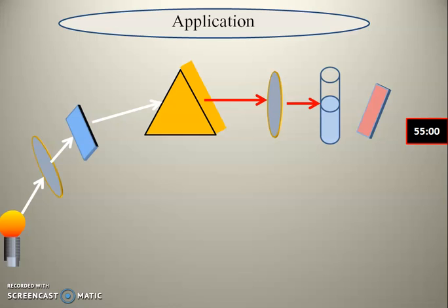The sample in the cuvette absorbs some part of radiation and remaining radiation is transmitted from the cuvette. The transmitted radiation from cuvette goes to photocell, where it is converted into current. The converted signal goes to measuring device, where it is converted as absorbance and is displayed.